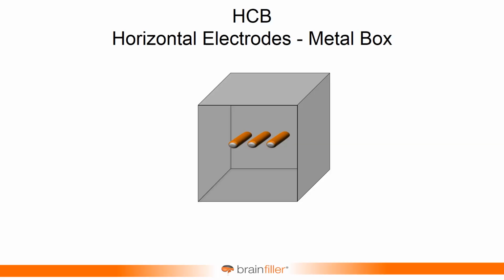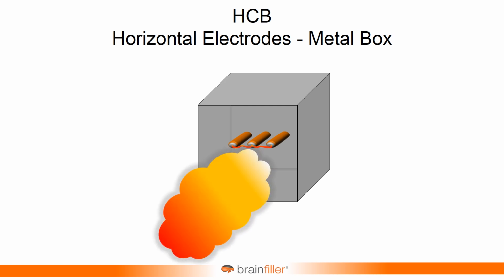And then we have the horizontal electrodes. And these are the electrodes pointed at you. And this is the most aggressive of the tests, because what's going to happen when you have horizontal electrodes, and this might be like bus stabs or something like that, and I have a few pictures I'll show you, is that the energy is going to run along the horizontal bus, and it's going to come off the end, basically being directed at the person that may be in front of it. Hopefully there won't be anybody in front of it. You should be standing off to the side, but it's coming out more aggressively. And so you have the arc, and then you have the energy that's being directly ejected straight out of the enclosure. And as I said, this is a lot more aggressive arc flash setup.